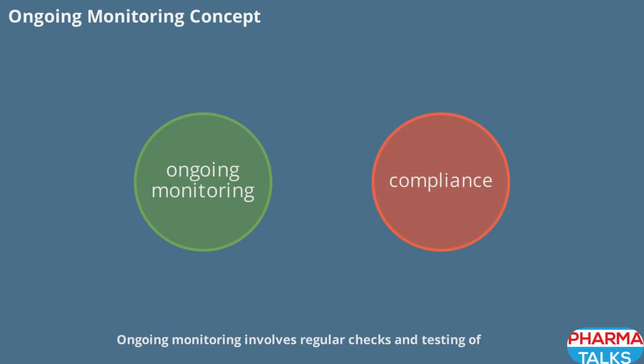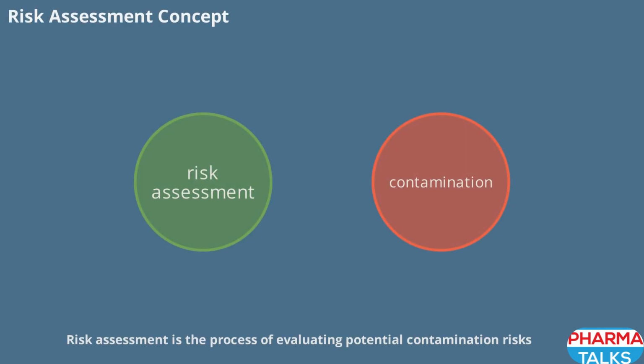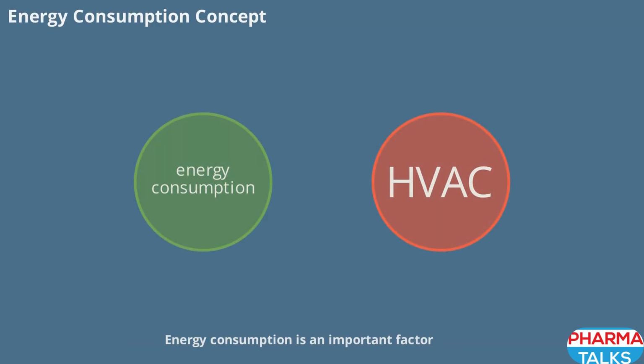Ongoing monitoring involves regular checks and testing of filters to ensure they continue to perform as required. This includes periodic integrity and leak testing, as well as documentation of all results for regulatory compliance. Risk assessment is the process of evaluating potential contamination risks in a cleanroom and determining the appropriate level of filtration. This assessment guides the decision to use HEPA or ULPA filters and is a key part of regulatory compliance. Energy consumption is an important factor when choosing between HEPA and ULPA filters. ULPA filters require more energy due to their higher resistance to airflow, impacting both operational costs and HVAC system design.